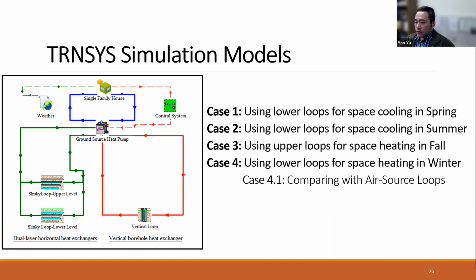Case 3 is to use the upper loop for space heating in the fall season. The idea is to minimize the use of the ground where the lower loop is buried before winter, to make sure the lower loop is ready for winter in order to maximize the system efficiency for space heating in cold weather, because it is a heating-dominated building.